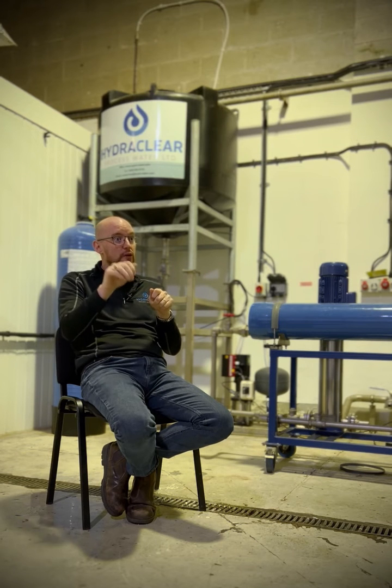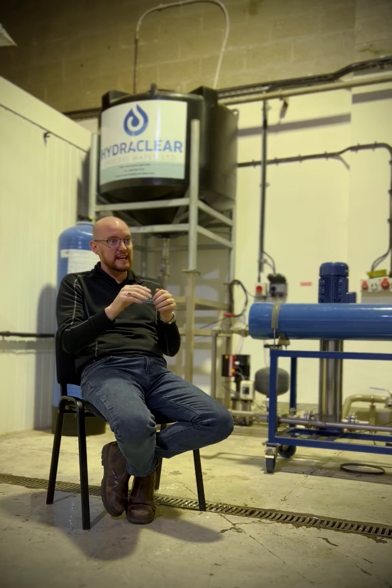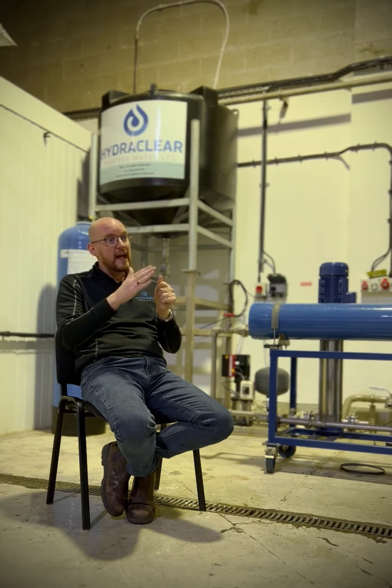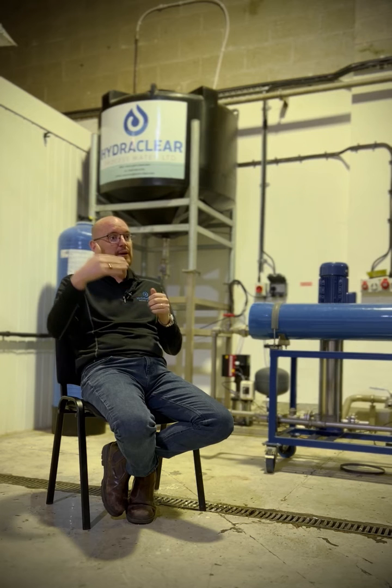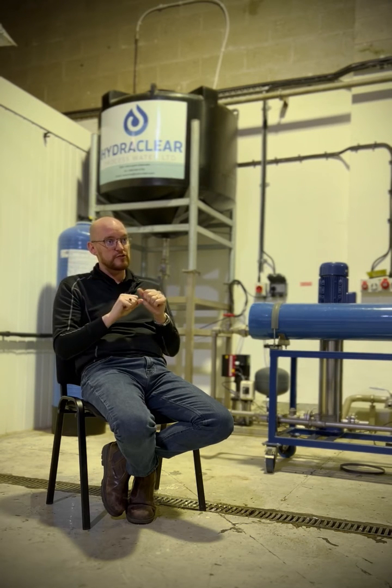So it's rejecting hardness. It's rejecting chloride. It's rejecting bacteria, microorganisms, total organic carbons. It's rejecting all of these things, and it's allowing only H2O or under a certain molecular or Dalton weight ion through this very specialized membrane. And at the end of it, we collect something that we call permeate, because it's permeated through the membrane, and we've got a treated water stream.